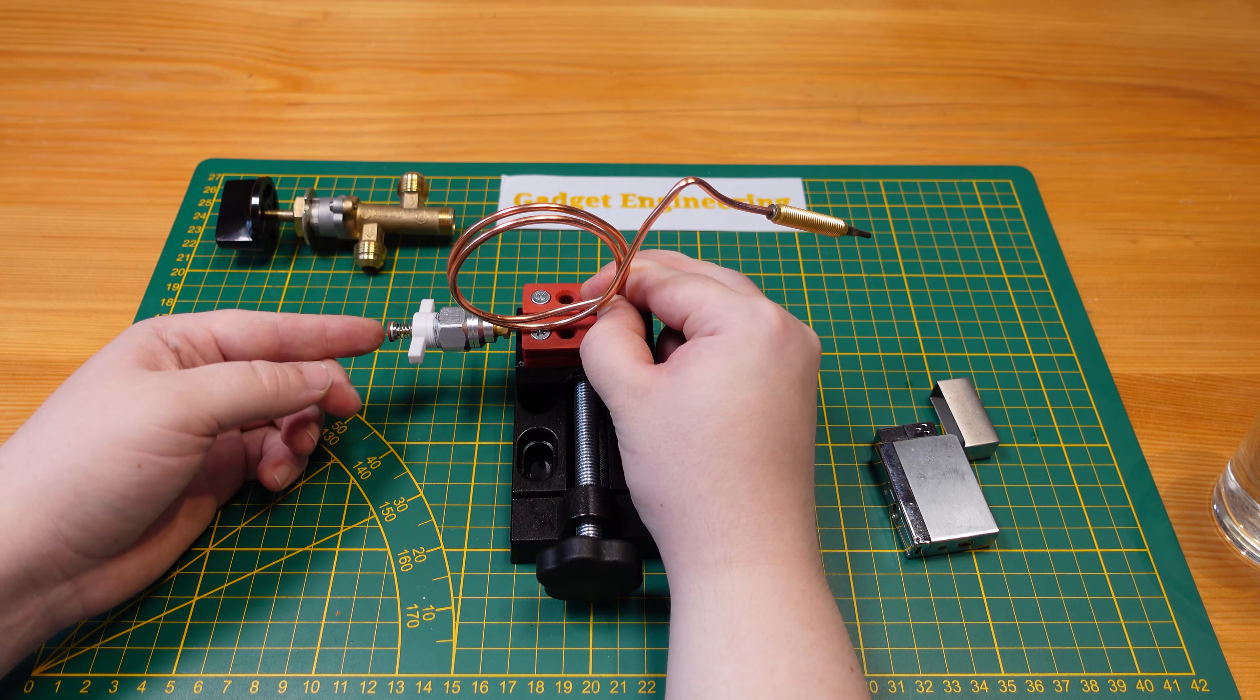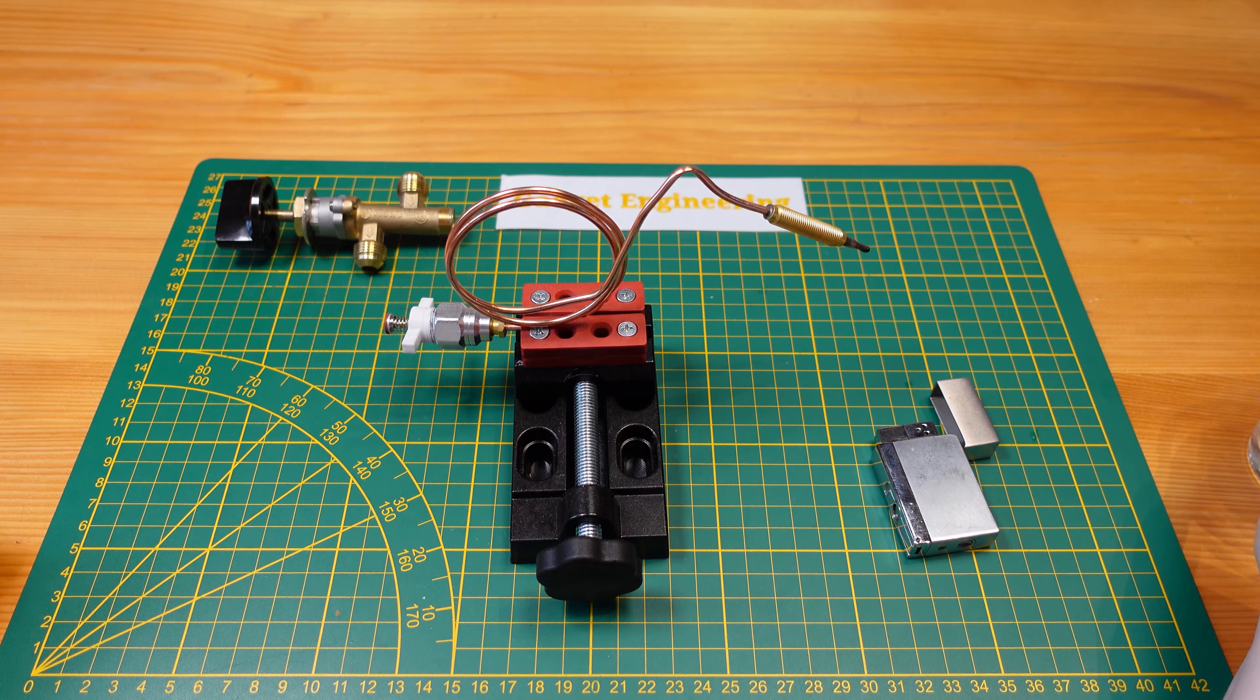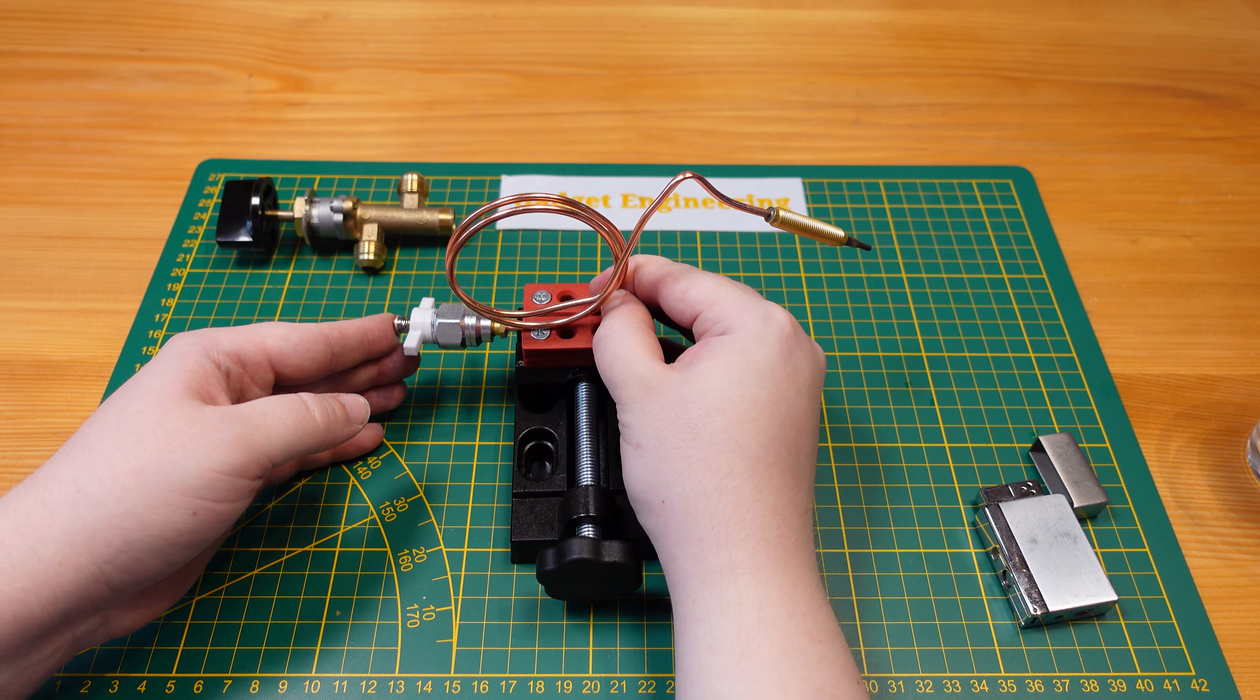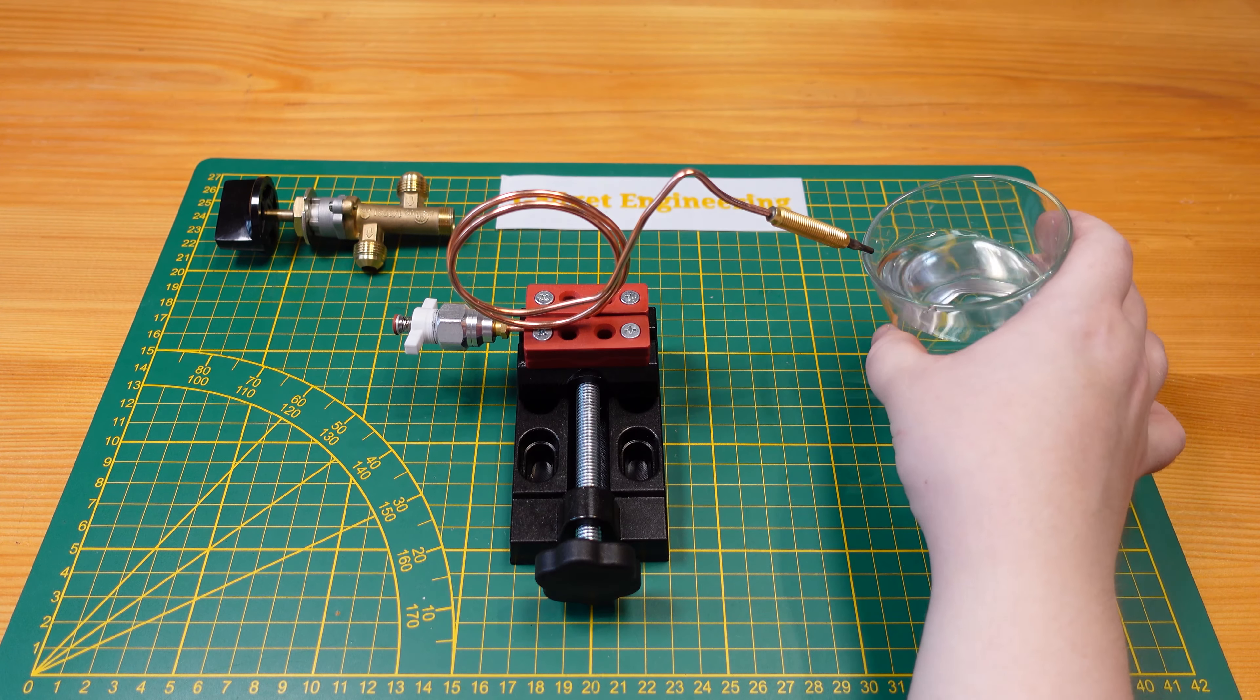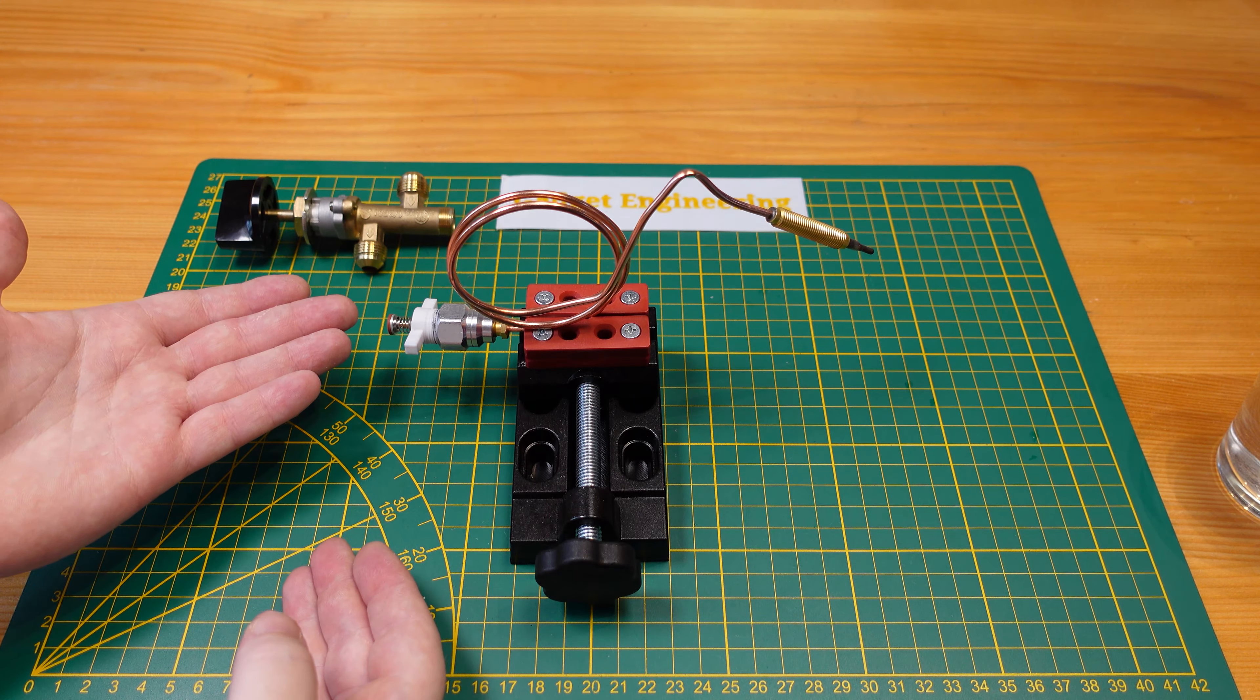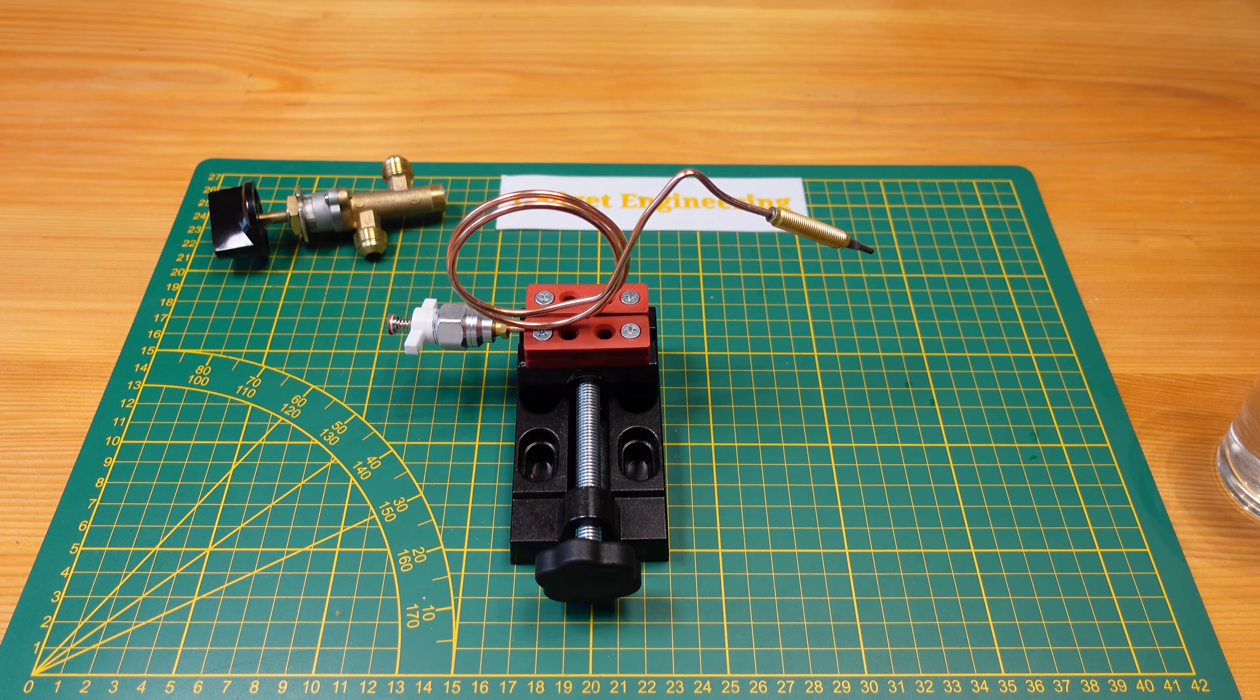So yes, I can pull it to release it. But when I push it back in, it still retains. And you can see if I rapidly cool it, it is released immediately. So just one more time, let's take a look at this. So I've heated it, that's probably enough thermal energy to latch it. Our valve is open. Once it cools, the spring is released, electrical current flow stops, the solenoid is not latching anymore, the valve closes, the burner is shut off, it's been blown out, no harmful gas is being released into your home.